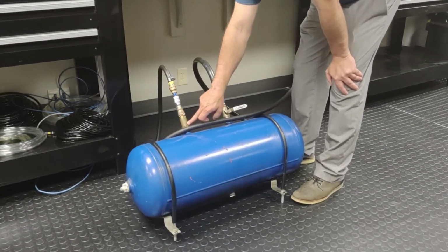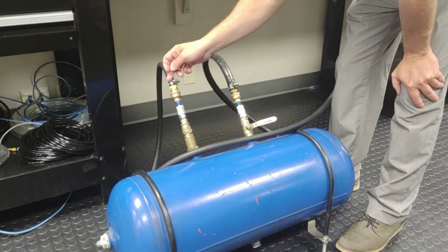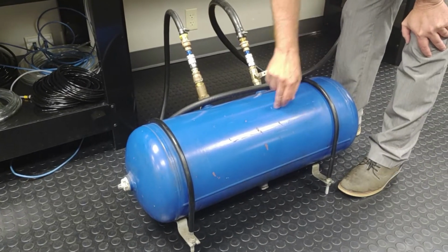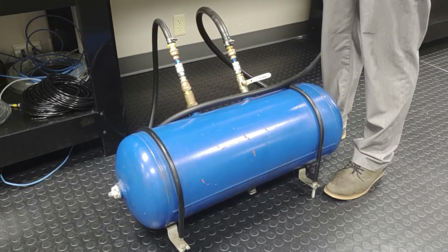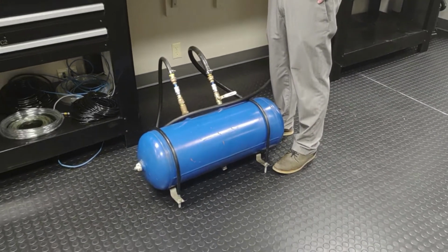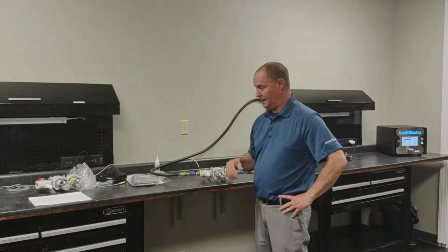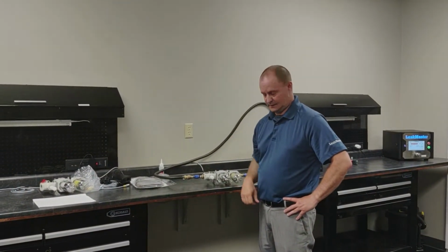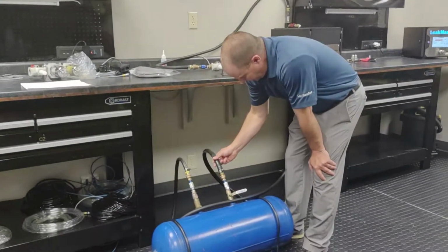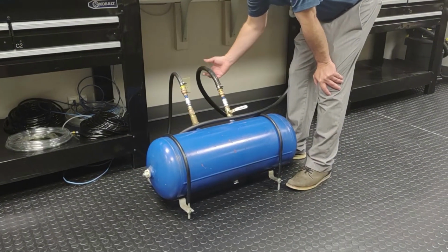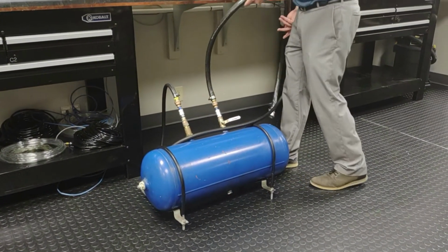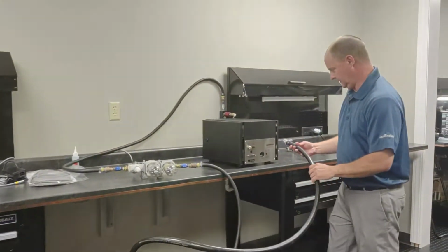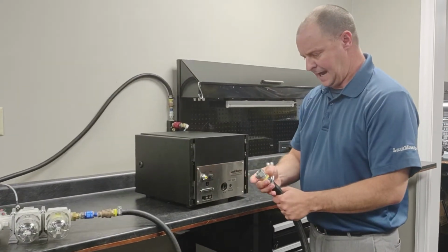We've got a check valve right here. This will allow us to put air inside the tank, but we can't remove any air from the tank. That prevents the other stations around us from robbing air from our system and affecting results on our leak test. Now we're going to come out of the ballast tank and into the back of the leak tester.